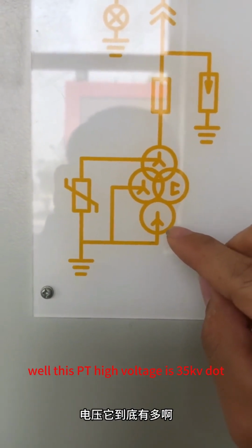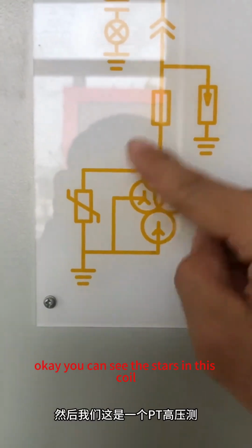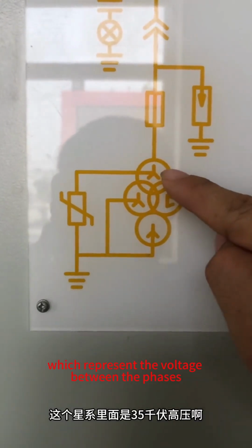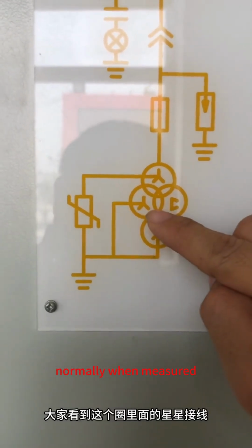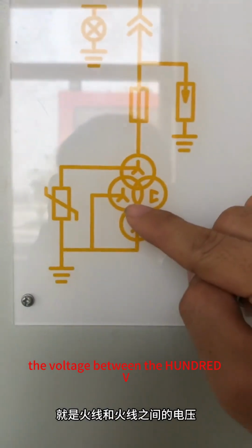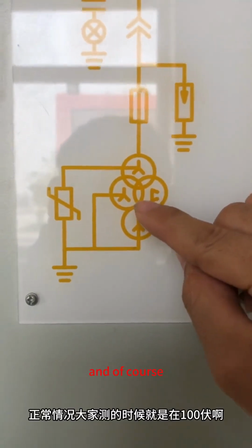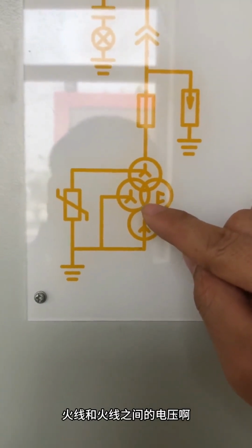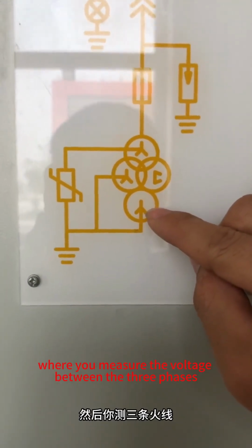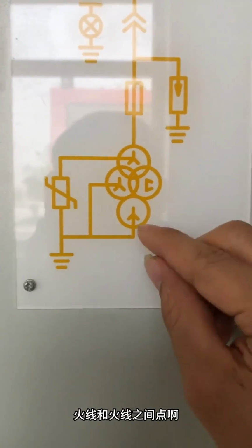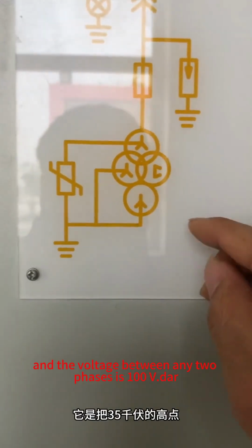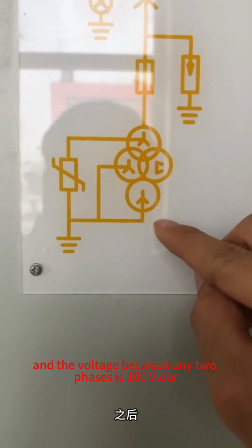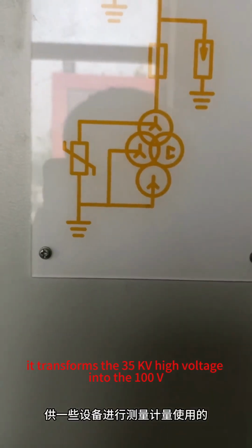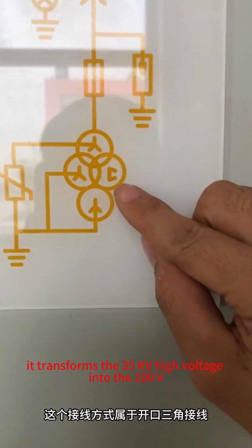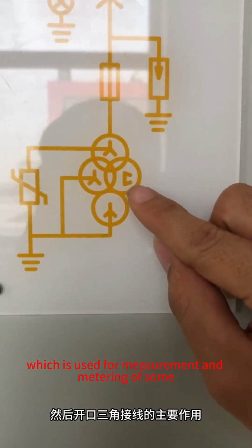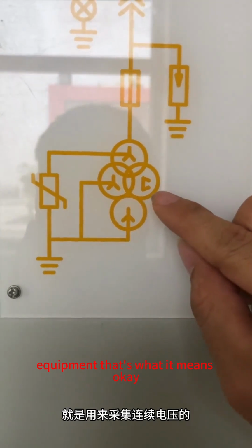Well, this PT high voltage is 35 kV. Okay, you can see the stars in this coil, which represent the voltage between the phases. Normally, when measured, the voltage between phases is 100V. And of course, this is the star wiring, where you measure the voltage between the 3 phases. The voltage between any 2 phases is 100V. It transforms the 35 kV high voltage into 100V low voltage, which is used for measurement and metering of some equipment. That's what it means.